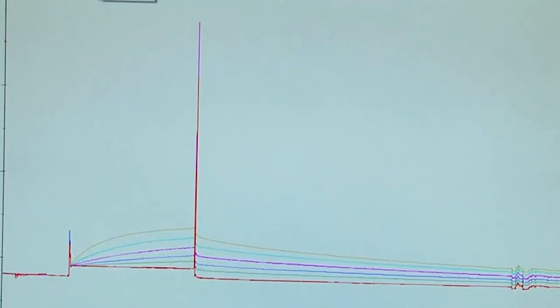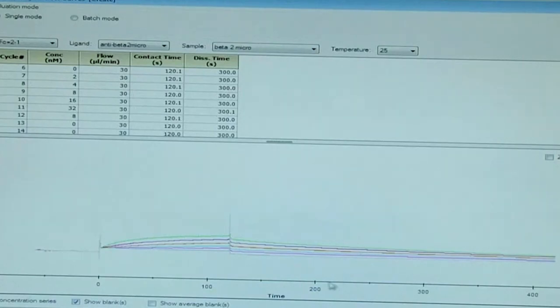Select surface bound. The data is shown here. You can see the different cycle numbers, different concentrations of beta 2M. The flow rate injected was 30 microliter per minute, contact time of 120 seconds, and dissociation time of 300 seconds.